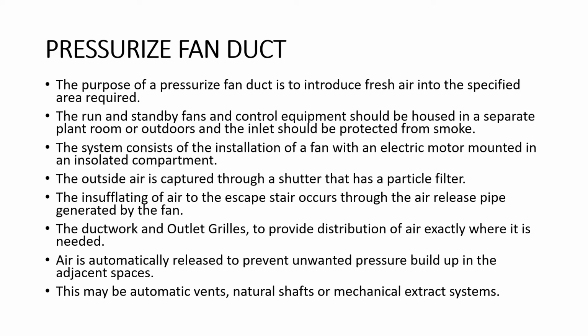The insufflating of air to the escape stair occurs through the air release pipe generated by the fan, the ductwork, and outlet grills to provide distribution of air exactly where it is needed. Air is automatically released to prevent unwanted pressure build up in the adjacent spaces. So this may be automatic vents, natural shaft, or mechanical extract systems.